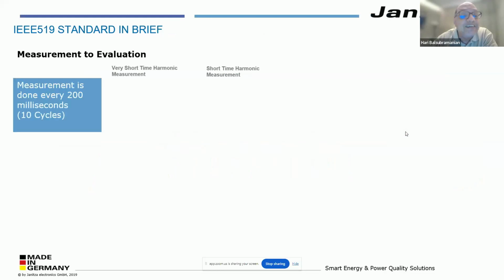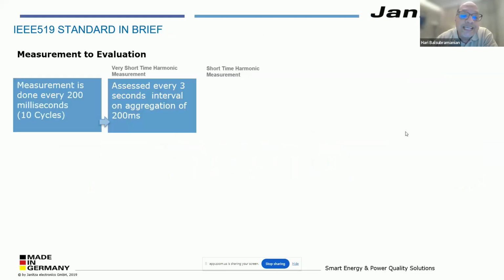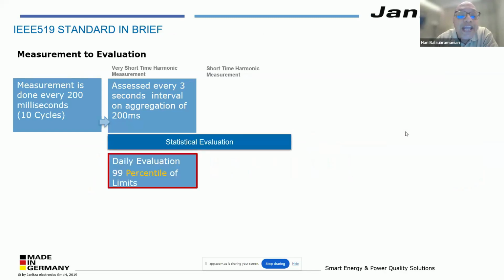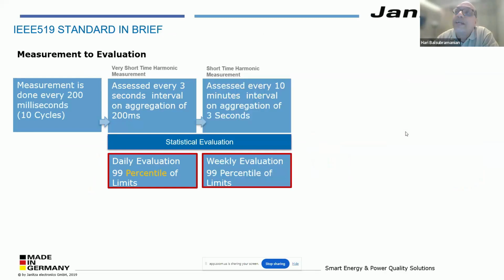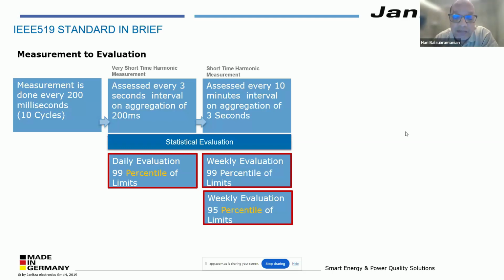So how do we do the statistical evaluation? Measurement is done every 200 milliseconds, as I said, every 3 seconds it is aggregated, and then on a daily basis we calculate the 99th percentile value. This is one statistical evaluation, and it has its own limits. So the daily evaluation of the 99th percentile has its limits, and then you have a 10 minute value, taken from the aggregated 3 second values, and again you calculate for a weekly evaluation the 99th percentile limits and 95th percentile limits.